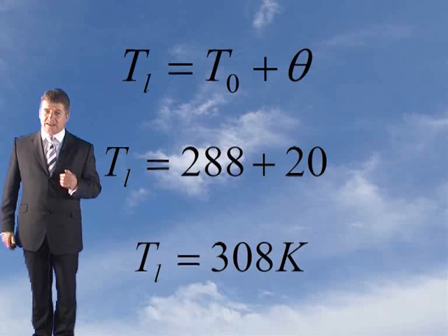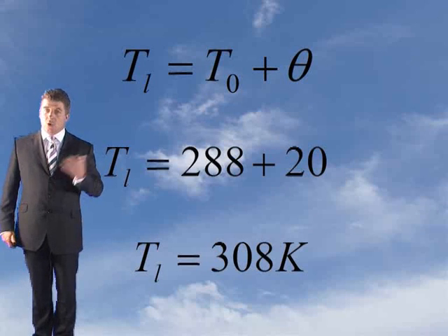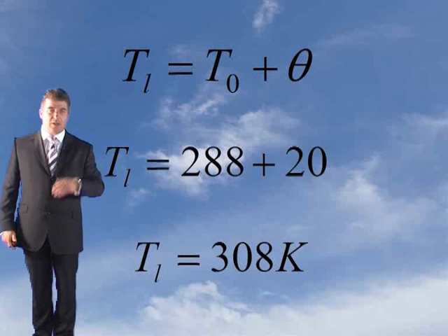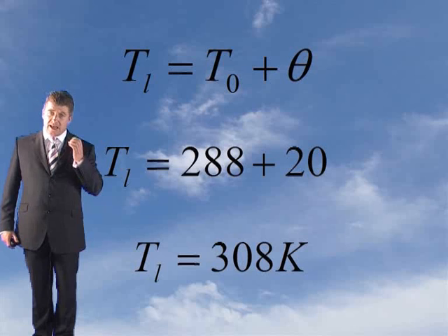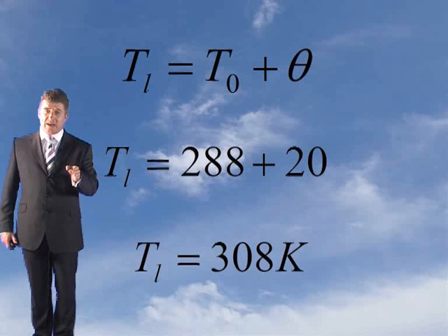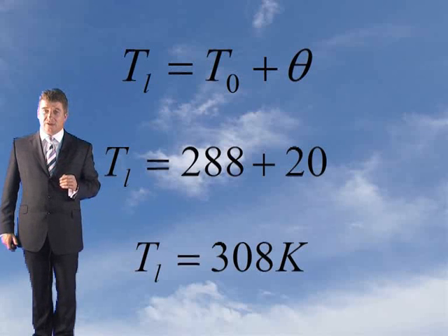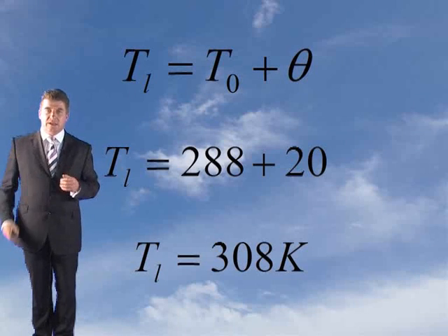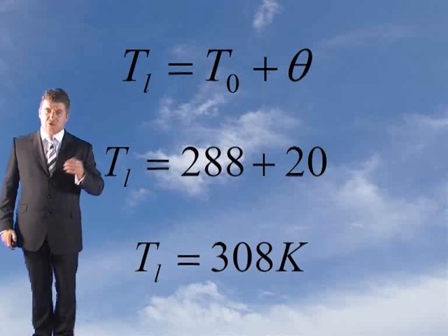Don't forget, it's important to remember at this point, if the smoke was over 200 degrees C, it's untenable for life safety. Well, in this case, it's well below that. And like I say, it's still got the buoyancy at a 20 degree increased theta value. Anything less than 20 degrees, you can't use natural. And in fact, really, you shouldn't be losing mechanical ventilation unless you've got other factors. 20 is the critical factor. You've just met the 20 degrees, so it does do that.